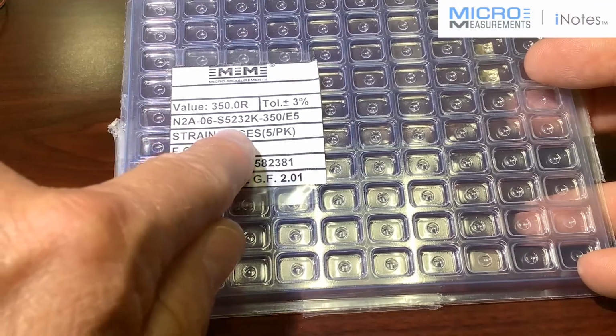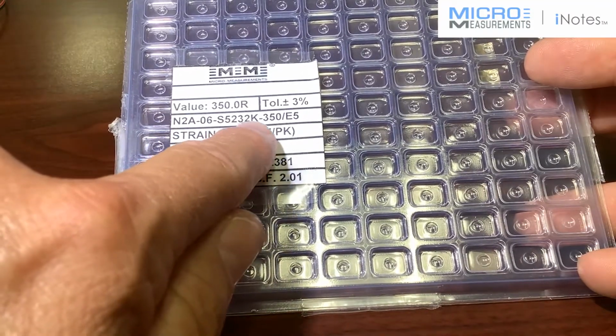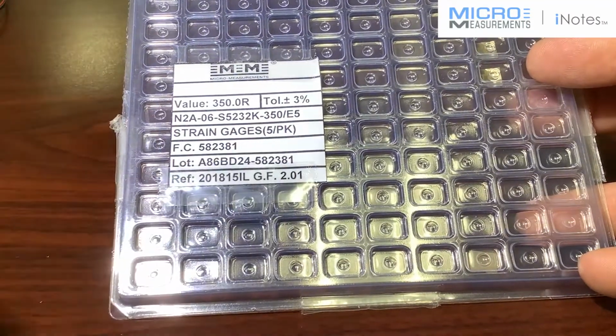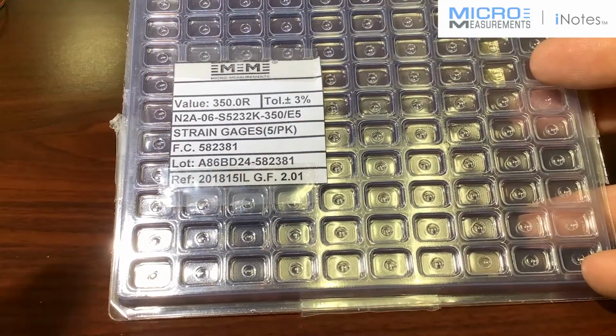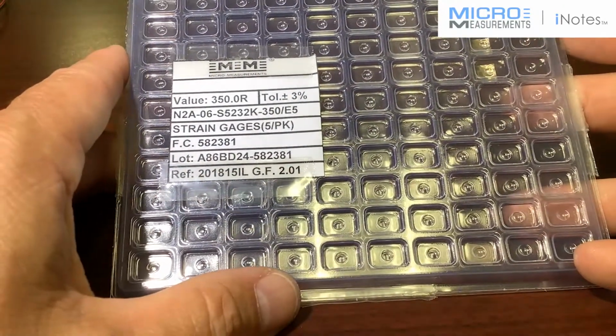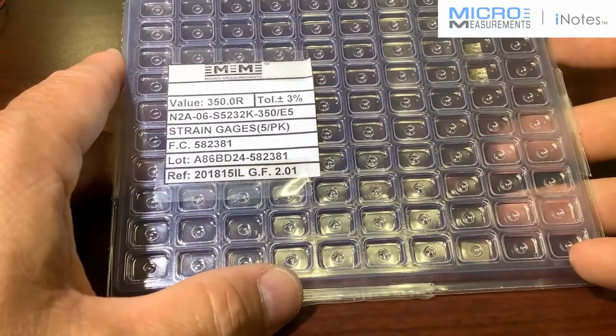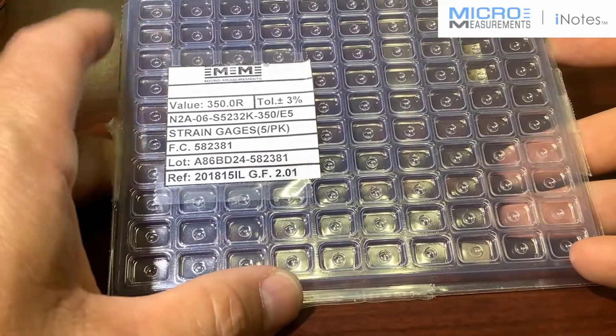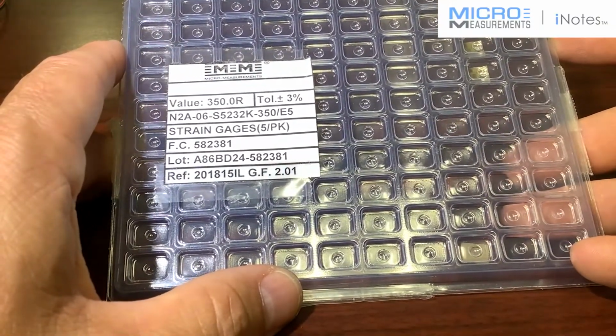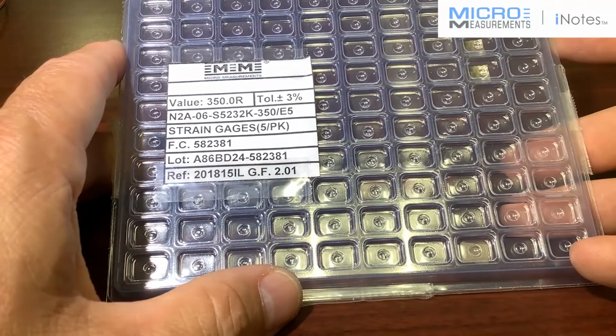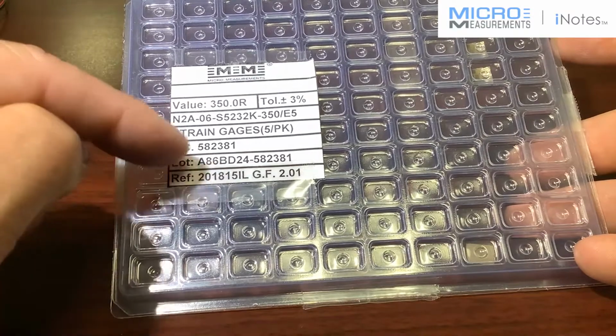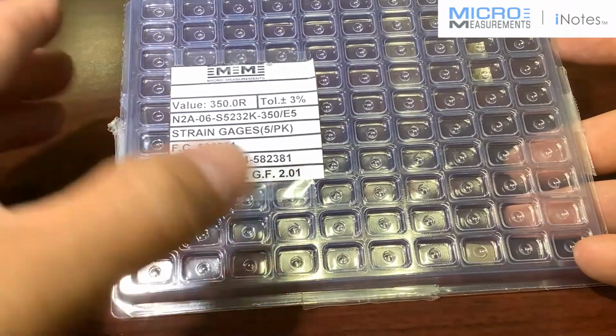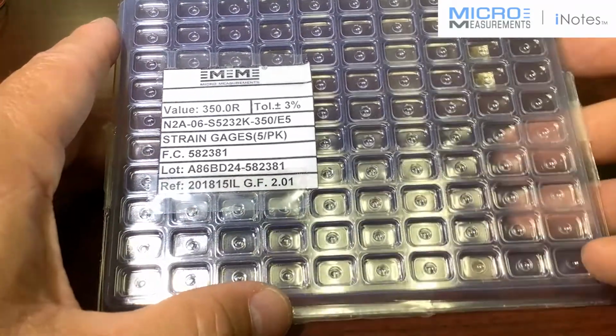The strain gauge in this package is an N2A06S5232K-350/E5. Basically, that's a 350 ohm constantan foil gauge with an E5 encapsulation. The resistance value is 350 ohms, plus or minus 3%. We've got some lot number information and reference numbers here as well, and it's got a gauge factor of 2.01.